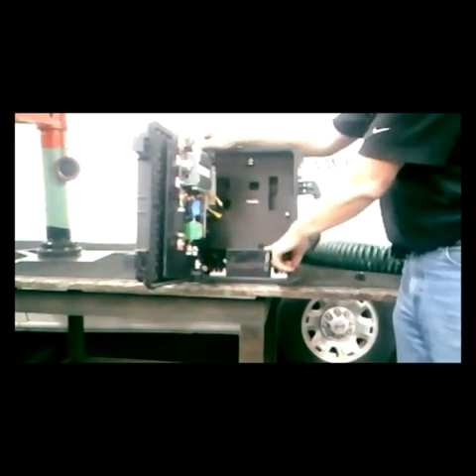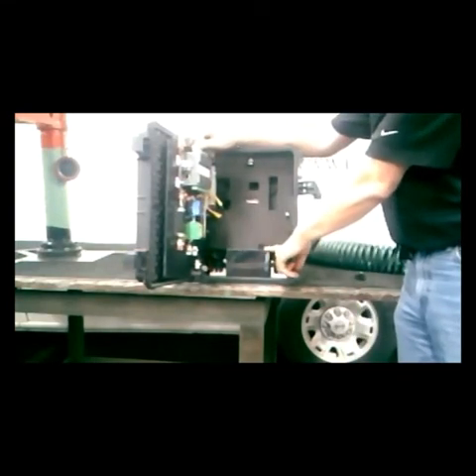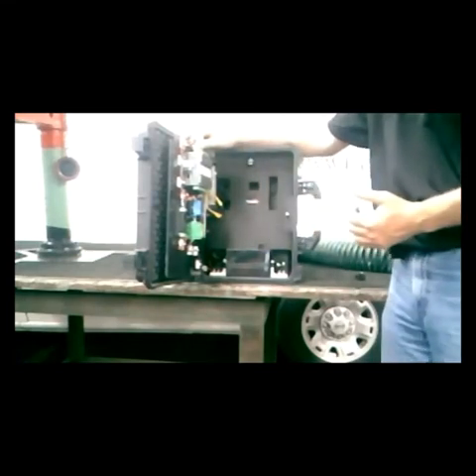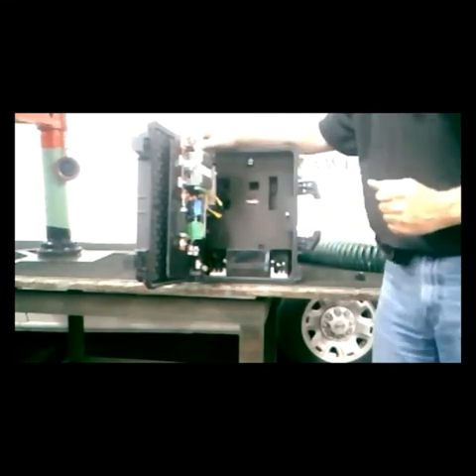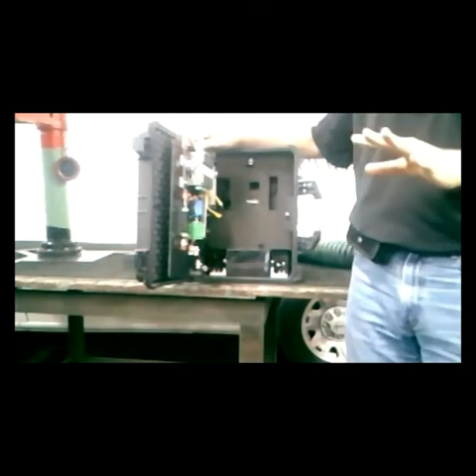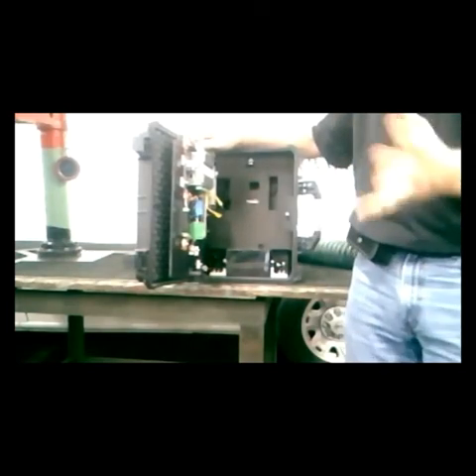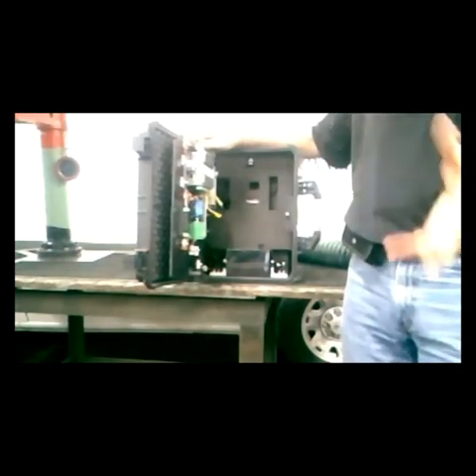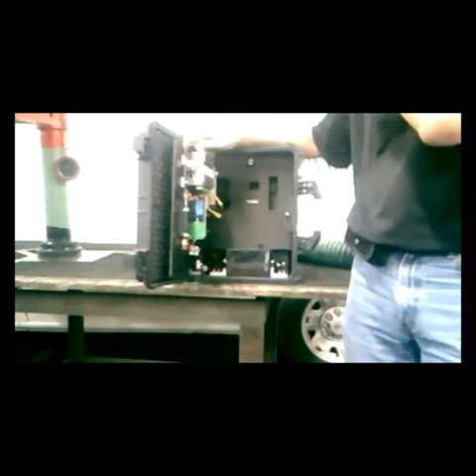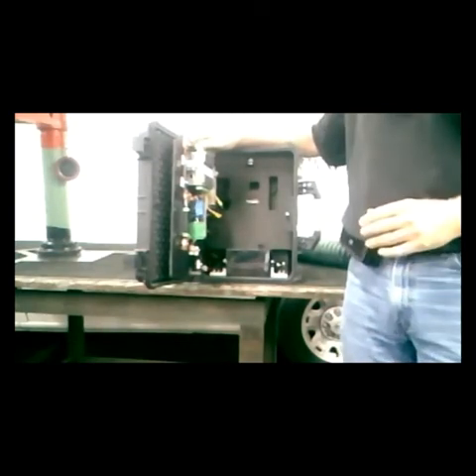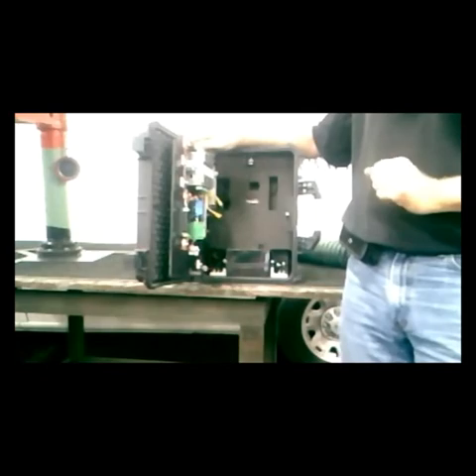It runs on a 24-volt lithium-ion rechargeable battery. I can hold up to 8 sensors in here, and it's scalable, so I can start with chlorine and then add a turbidity sensor later, or add a pH sensor later. It comes with temperature and PSI automatically, so chlorine, PSI, and temperature are the automatic three, and then I can add other things as I move forward from there.